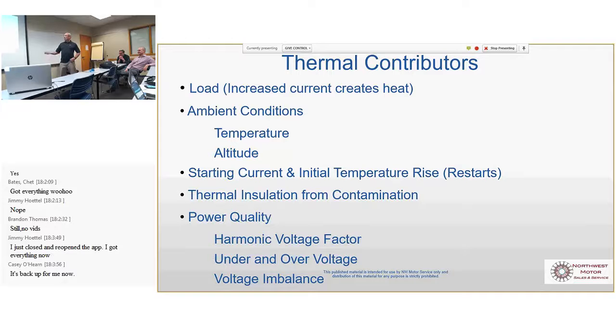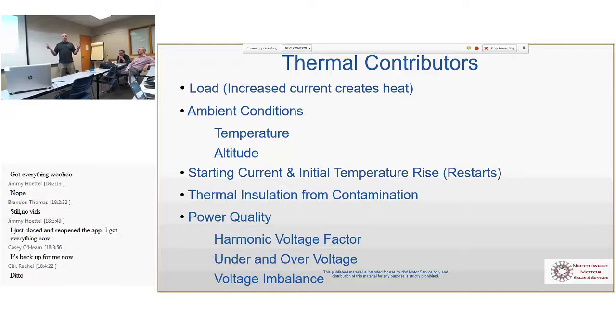You did that. So, thermal insulation from contamination - if your motor gets full of dust and other crud, like you were shown in those pictures, it's going to run much hotter, and it's not going to live as long because it can't cool itself off.